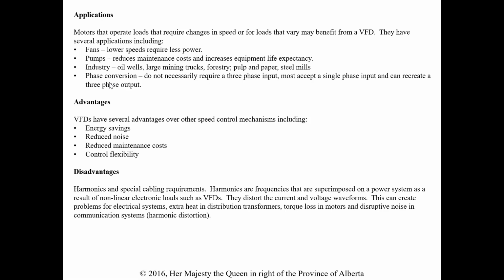VFDs were very expensive when they first came out, but they're obviously more widely used now and becoming a lot cheaper. Some advantages, again: energy savings, reduced noise, reduced maintenance cost, and control flexibility. Those are huge advantages for us to use a VFD over other speed control devices. Some disadvantages though that come with it: we get harmonics. Harmonics are an issue, and we have special cabling requirements.